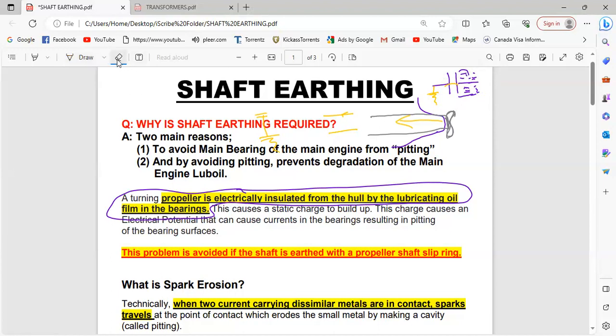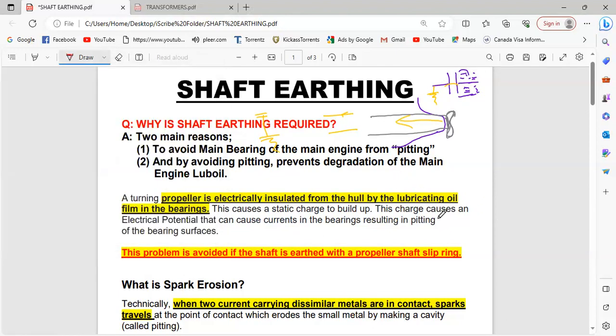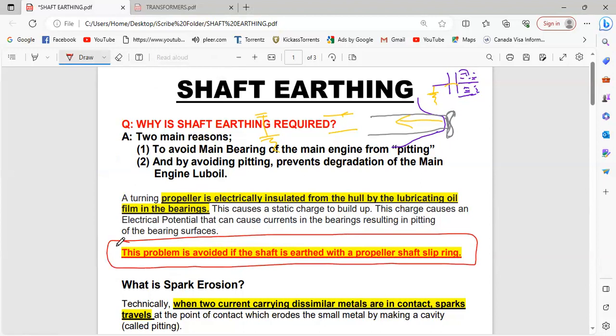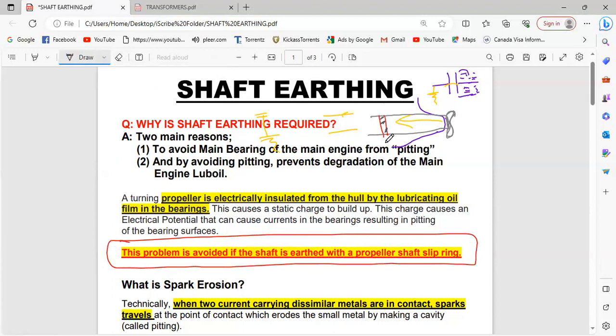In order to avoid this particular problem, we have what is called shaft earthing. Somewhere just before the intermediate bearing, you have a slip ring, a certain metal, mostly stainless steel, wrapped around the shaft, and then you have your brushes. Those brushes take the current down and earth it, so yes, the current will flow.